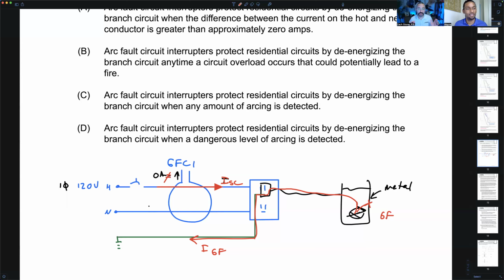Exactly. And that's when the GFCI will trip either the circuit breaker, if it's built into the circuit breaker, or there's a switch inside the receptacle. Anytime you see the test and reset button on a receptacle, that's how you know it's a GFCI. If it's code compliant, a lot of times there has to be a sticker that says GFCI. You can either buy a GFCI breaker, which provides ground fault protection on the whole circuit, because this sensor device is right up at the breaker. Or another common thing is you can buy one GFCI receptacle, and then every receptacle you wire off of that GFCI receptacle will still be protected by it. It acts like the GFCI breaker, basically. It can still look at differential current for everything going out.